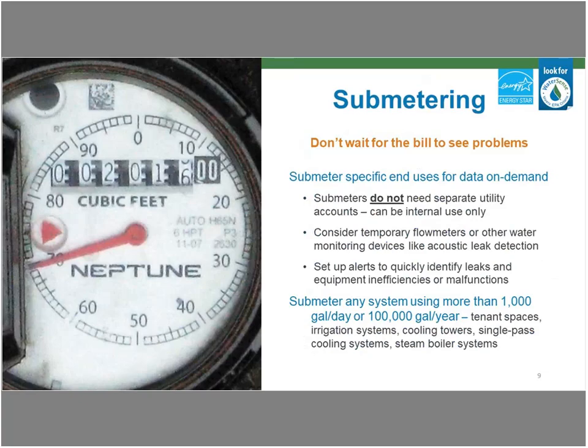Water meters are a vital tracking and measurement tool that can be used to track water use within a facility. You make sure that each source of water that's supplied by the utility is metered and tracked separately. So some utilities offer reclaimed water, for example. In some facilities, there's only one meter for the entire building called a master meter. So it can be very helpful to also install sub-meters on major water-using areas or systems such as tenant spaces, cooling towers, or irrigation systems. It's easier to spot areas to reduce water when you're accurately measuring and monitoring it.